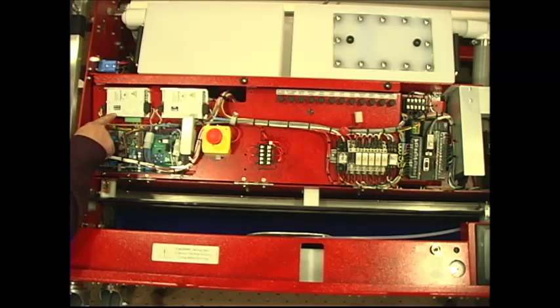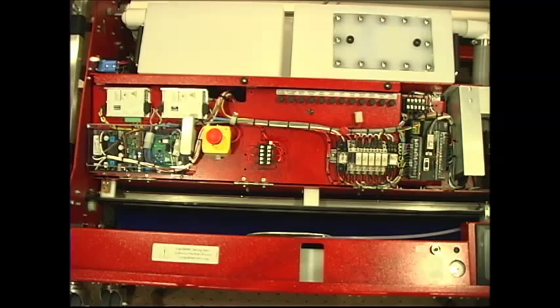The one on the left controls the head drive motor. The one on the right controls the oil pump motor. The bottom left underneath the cover, that is the speed control for the main drive motor. As you'll notice, there's a power indicator light and also a status light. The status light will indicate, as far as troubleshooting wise, in the manual and also in the touchscreen, there is a chart to view what the status light means in case there's an error.